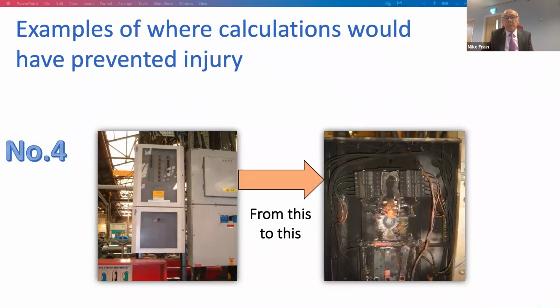There are several examples in my book, and it comes under chapter 12, myths and mistakes, from the guide, where calculations would have picked the problems up before it caused injury. The catastrophic failure of the capacitor, there's also an environmental injury. And in this case, it's an apprentice who was burned while connecting cables into a distribution board. And all three incidents would have been averted had the upstream protection arrangements been examined as part of an incident energy study. Or, as I'll show you later, some sort of dynamic risk assessment before people start working on there. And of course, I'm sure you may have picked up that perhaps a risk assessment wouldn't have looked at the incident energy in this particular case, but why he was doing it in the first place.